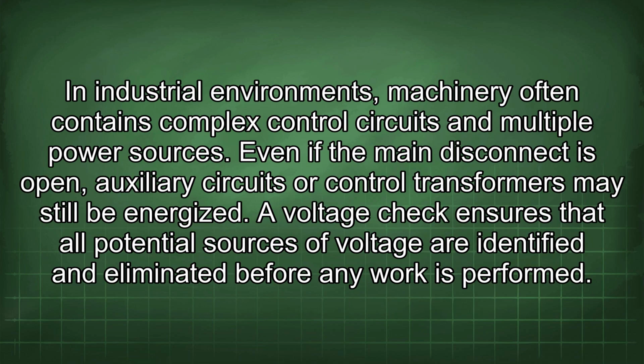In industrial environments, machinery often contains complex control circuits and multiple power sources. Even if the main disconnect is open, auxiliary circuits or control transformers may still be energized. A voltage check ensures that all potential sources of voltage are identified and eliminated before any work is performed.